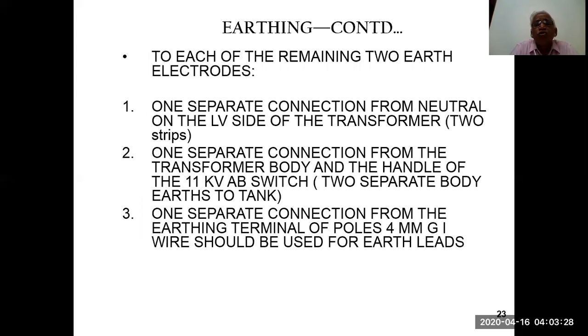Earthing connections to each of the remaining two earth electrodes: one separate connection from the neutral of the LV side of the transformer; two strips you have to provide. One separate connection from the transformer body and the handle of the 11 kV AB switch. Two separate body earths to the tank you should give. And one separate connection from the earth terminal of the poles. 4 mm GI wire should be used for the earth leads.